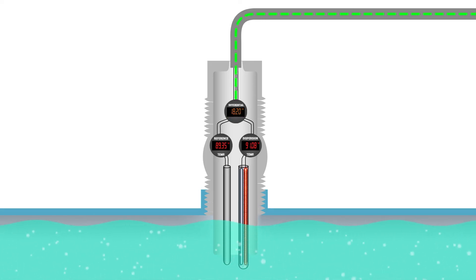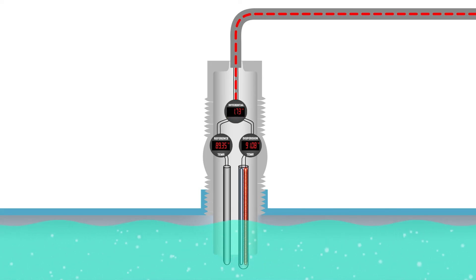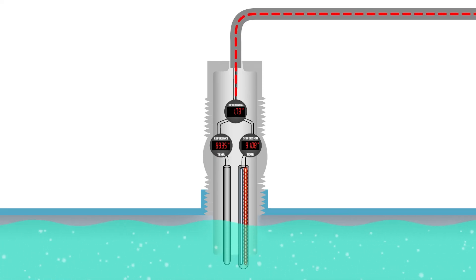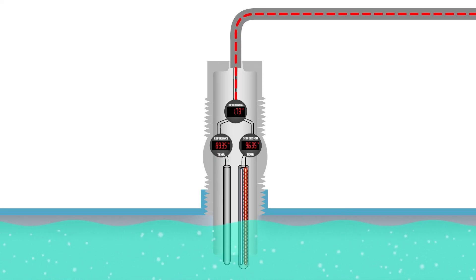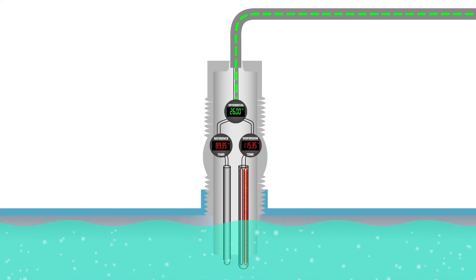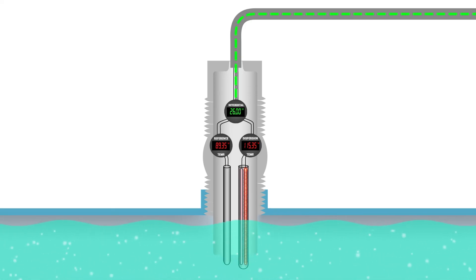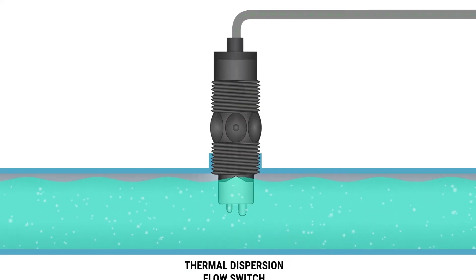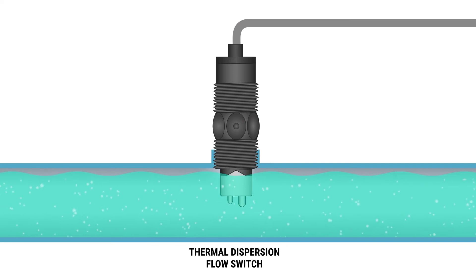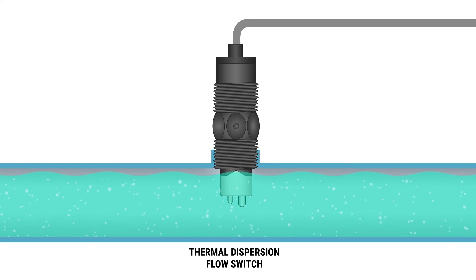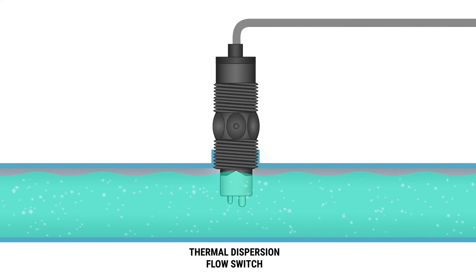A decrease in the temperature differential between the two sensors indicates that the flow rate exceeds the defined set point. When the flow rate drops, there's less cooling, which causes an increase in the temperature differential. Since a thermal dispersion flow switch has no moving parts, they have a much longer service life. However, they cannot be run dry, as with some mechanical flow switches.